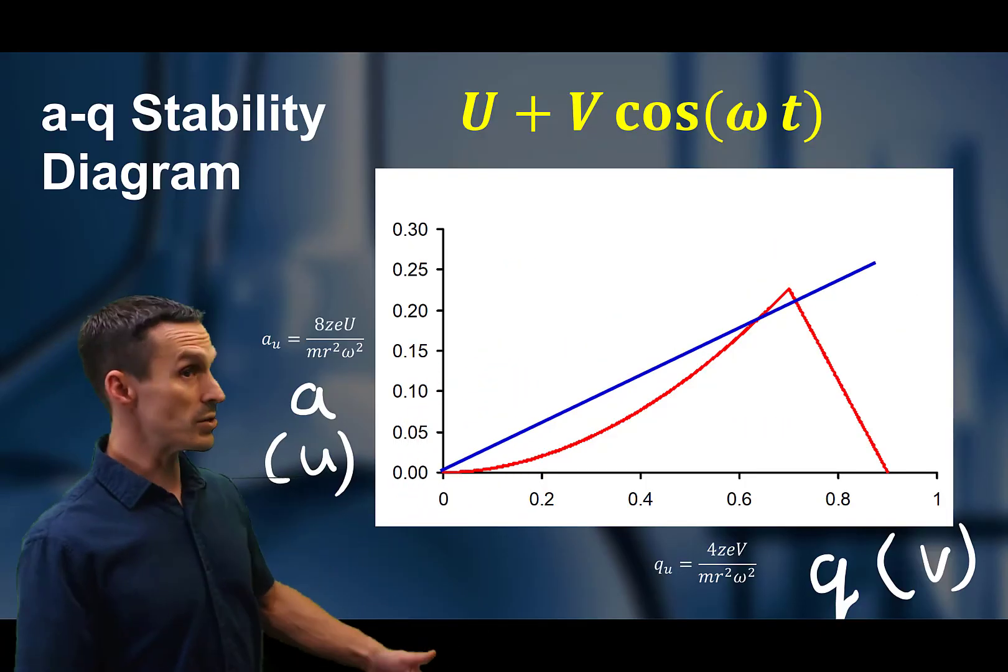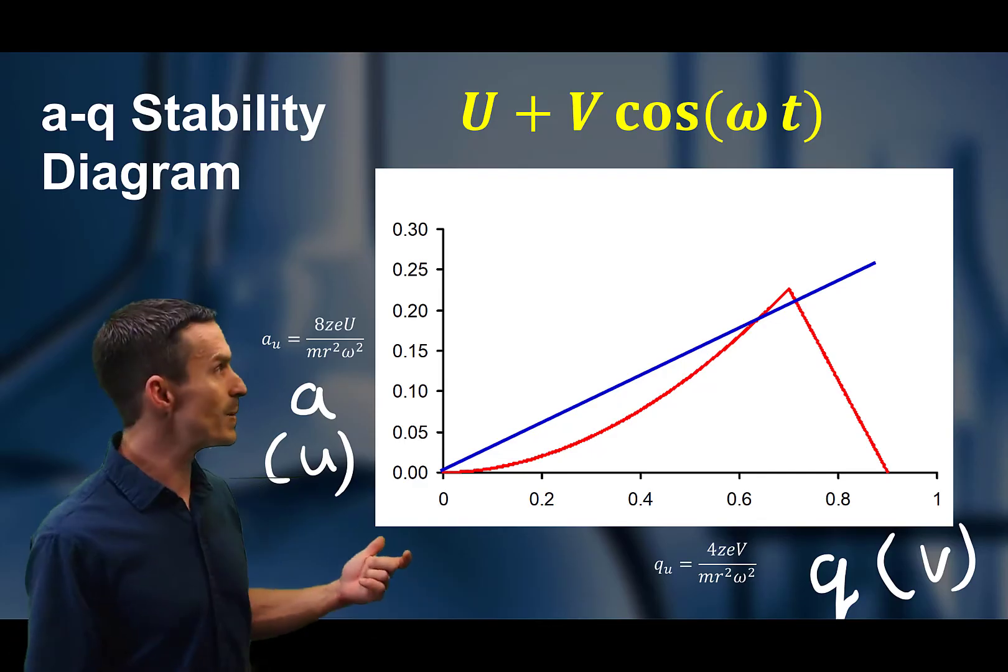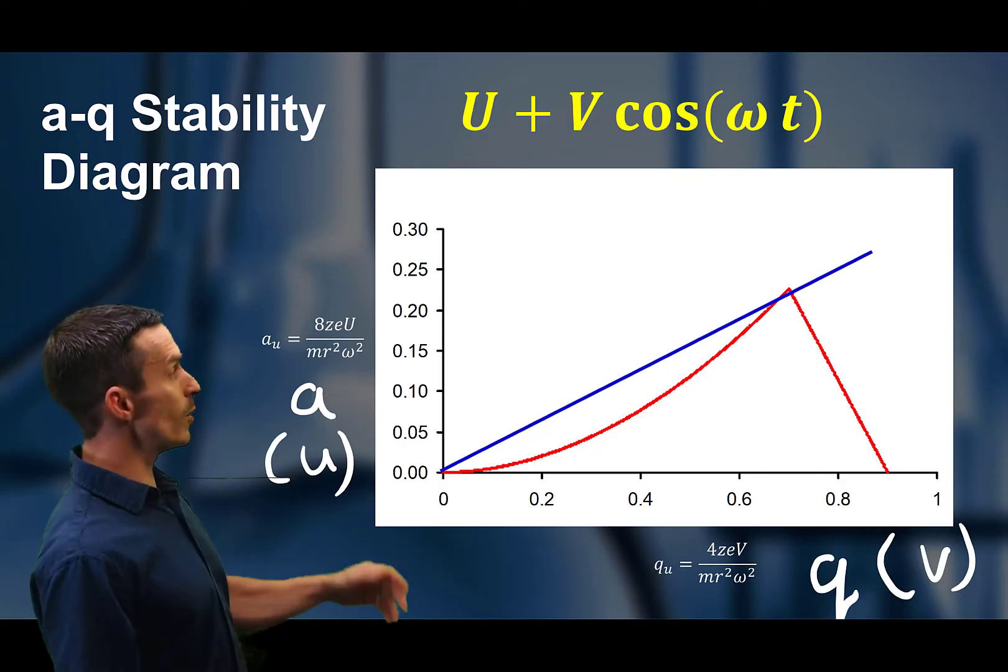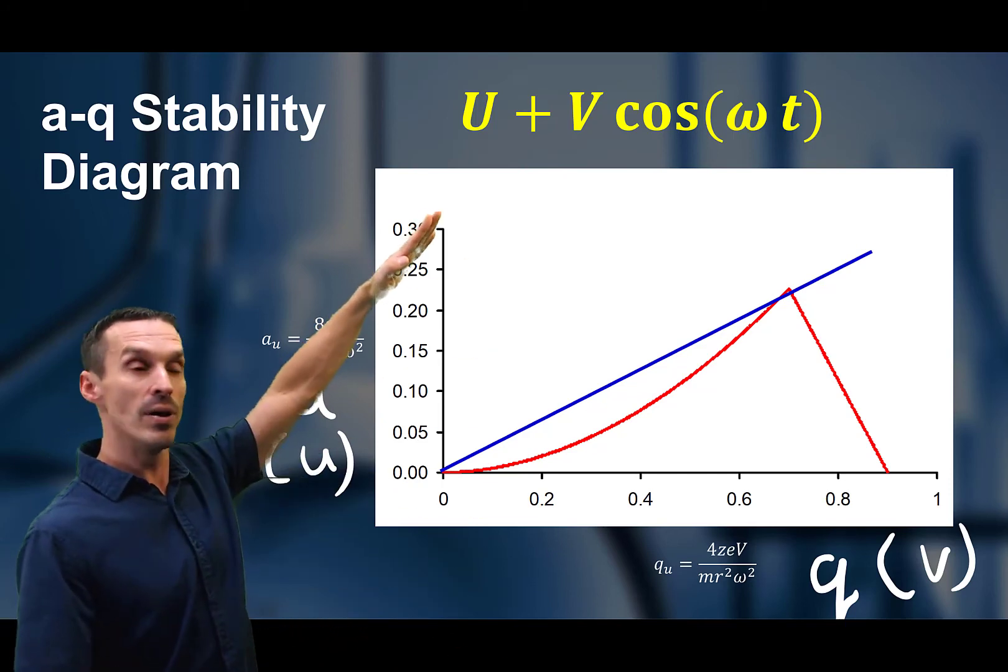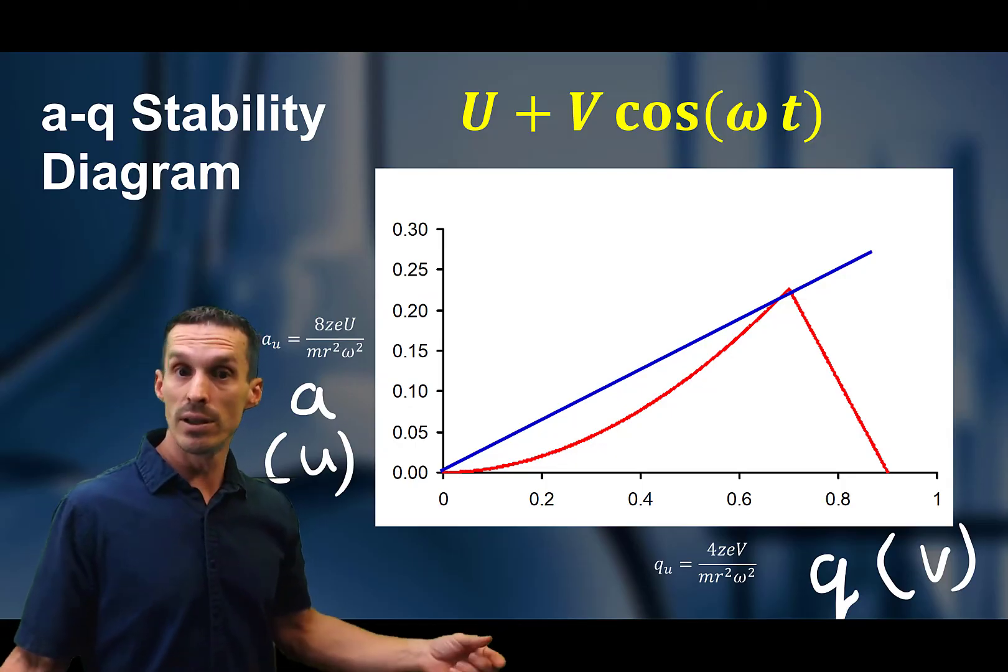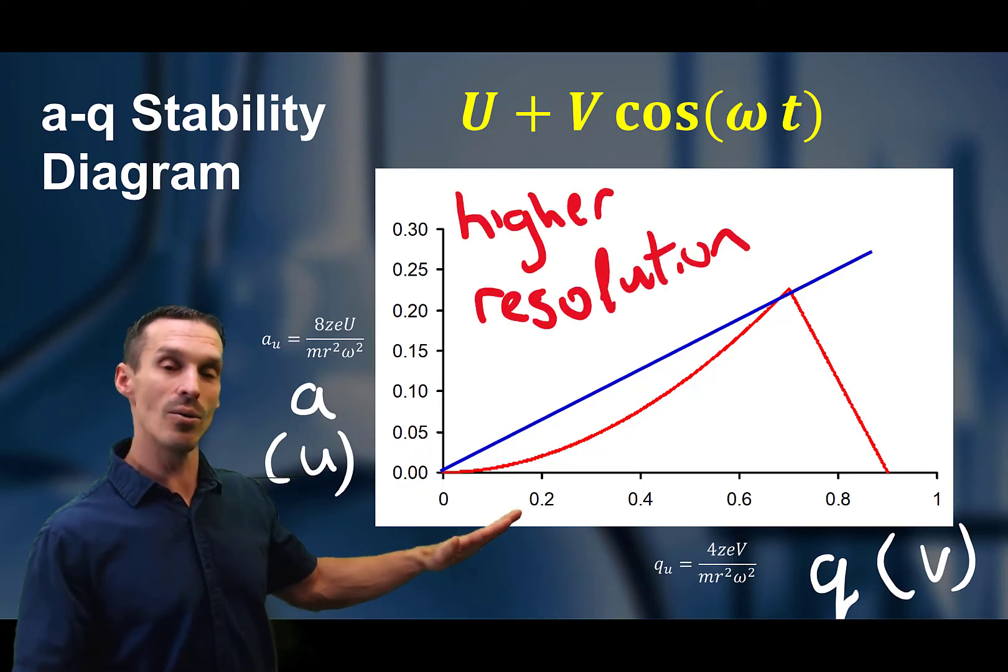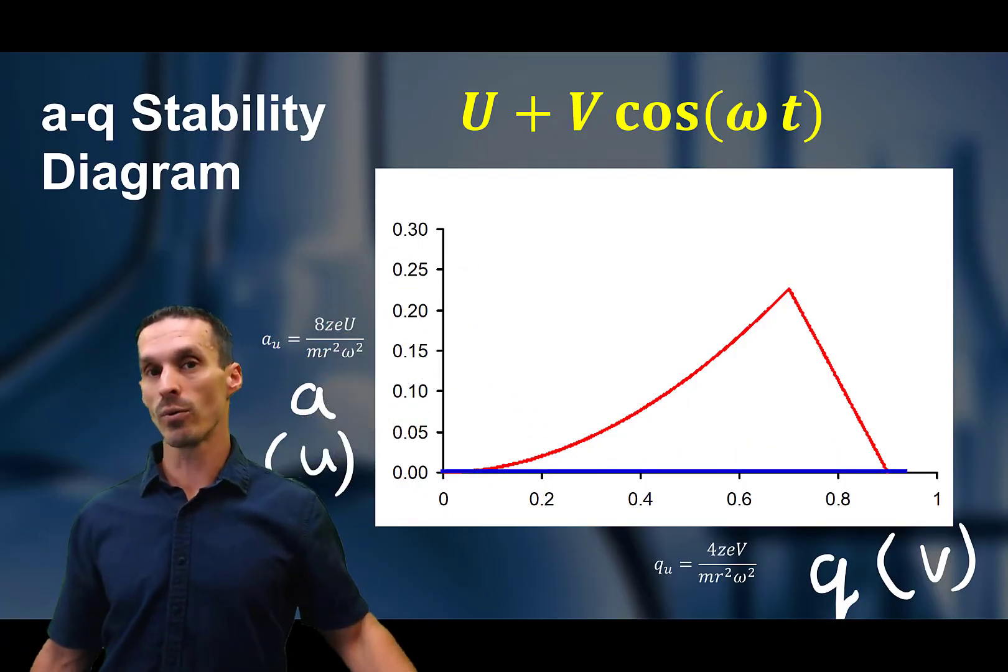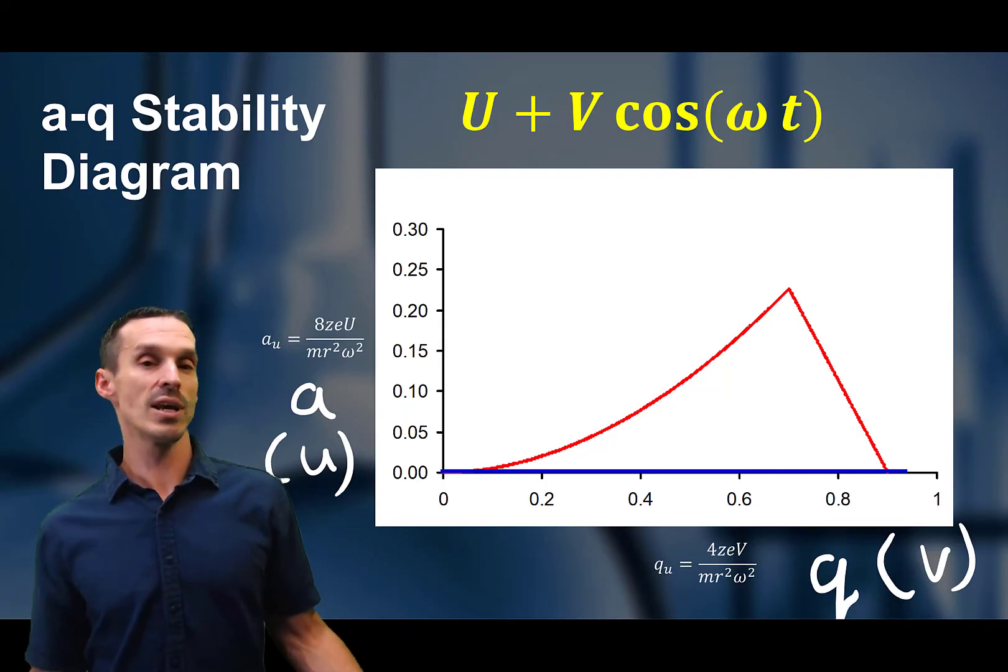Now the other thing you can do here is you can actually play with the parameters a little bit. So if I wanted to control the resolution, the resolution is basically how much of that line sits inside the stable region. So I can change the slope of that line. I'll do that by increasing U relative to V, and the slope goes up. So now, because it's only crossing just at a tip of that iceberg, the resolution is higher, the mass window is smaller. So I can change that resolution. I can go the other way, and I can go the extreme on the other way where the curve actually lies flat. When we do that, what we've done is we've set the magnitude of U, the a term, to zero. Or another way of saying this is that this is RF only.